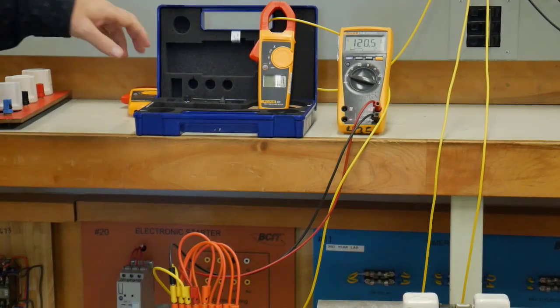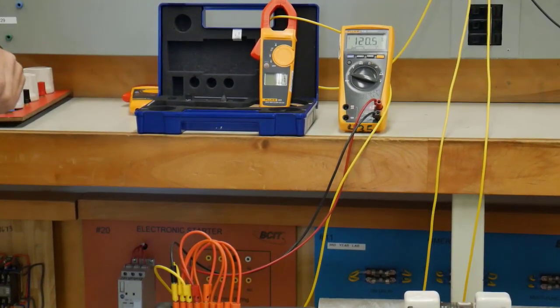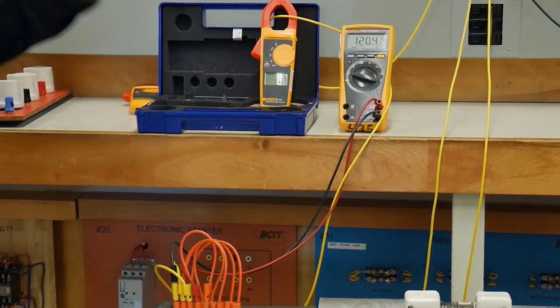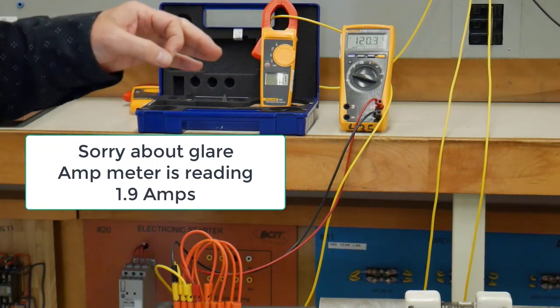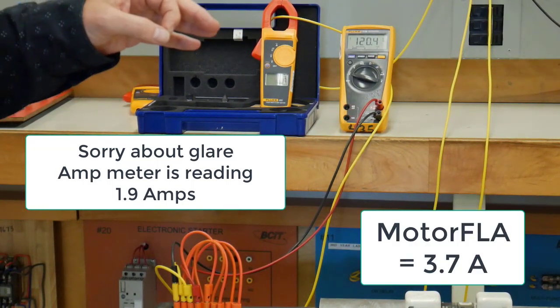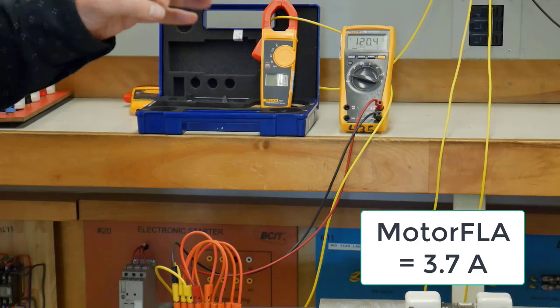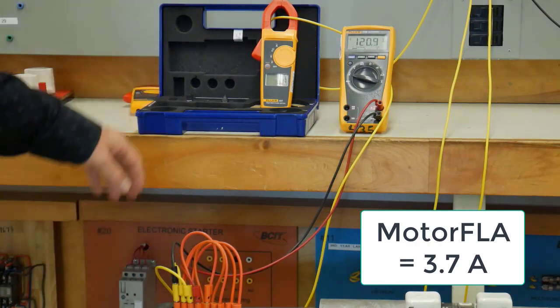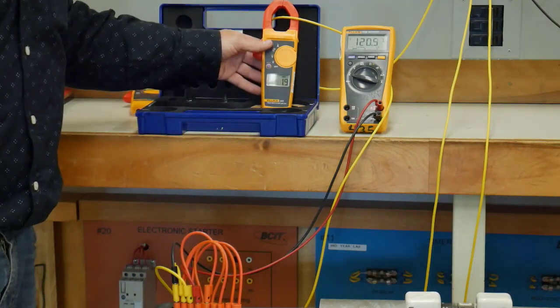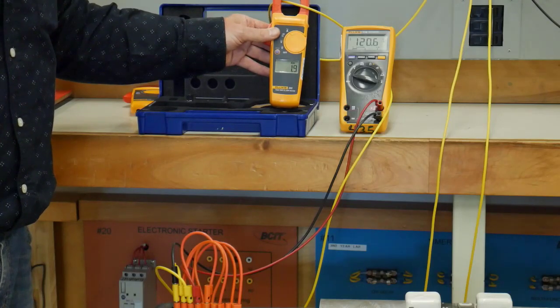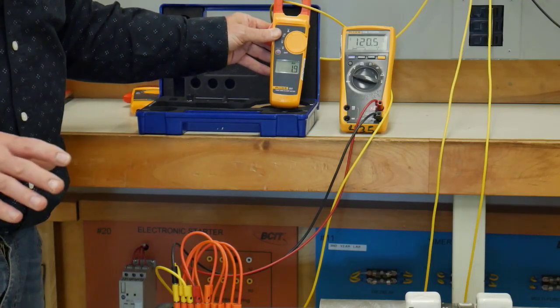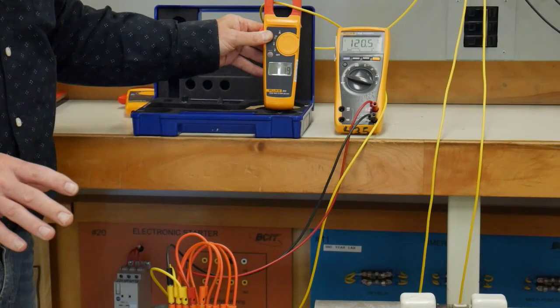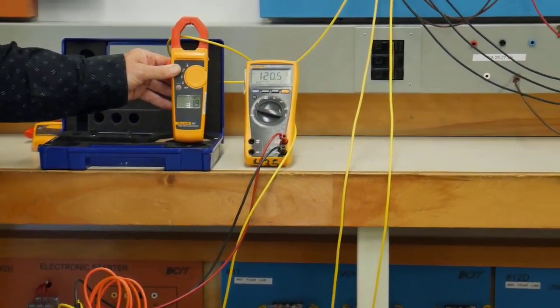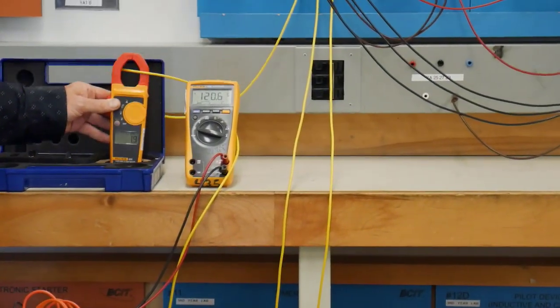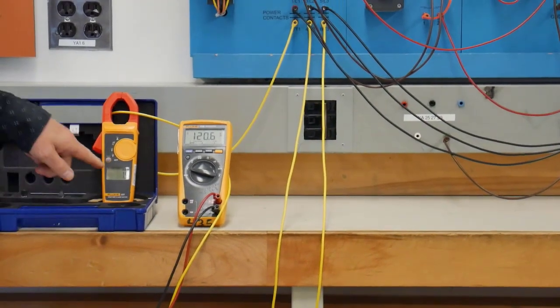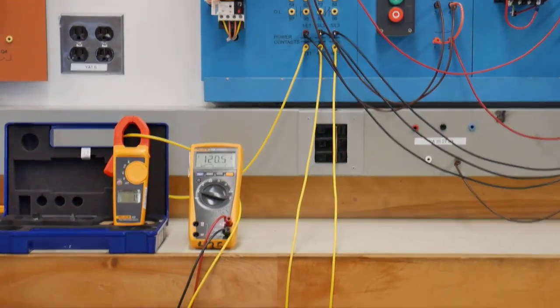Right now we have 1.9 amps, which is quite low. The FLA for this motor is 3.7 amps. Now we're going to watch the current here, lightly loaded, and we're going to create that single phasing condition. You can see the current reading okay?